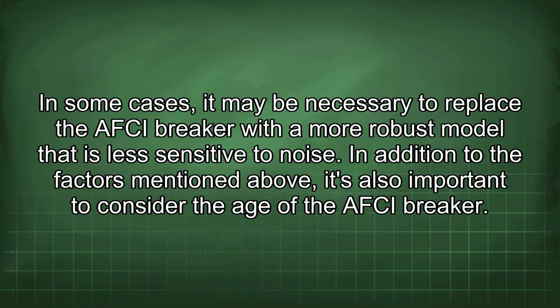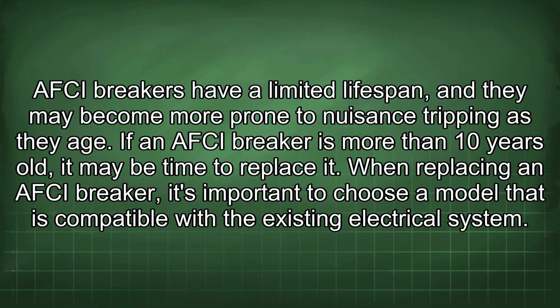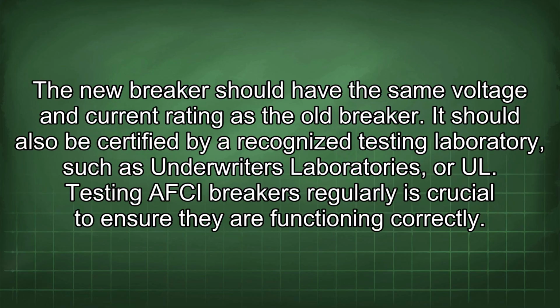In addition to the factors mentioned above, it's also important to consider the age of the AFCI breaker. AFCI breakers have a limited lifespan, and they may become more prone to nuisance tripping as they age. If an AFCI breaker is more than 10 years old, it may be time to replace it. When replacing an AFCI breaker, it's important to choose a model that is compatible with the existing electrical system. The new breaker should have the same voltage and current rating as the old breaker. It should also be certified by a recognized testing laboratory such as Underwriters Laboratories, or UL. Testing of AFCI breakers regularly is crucial to ensure they are functioning correctly.